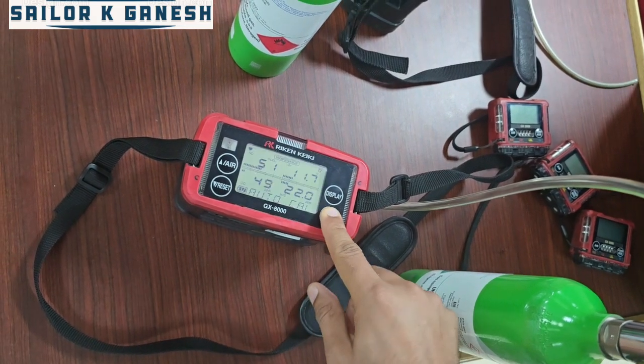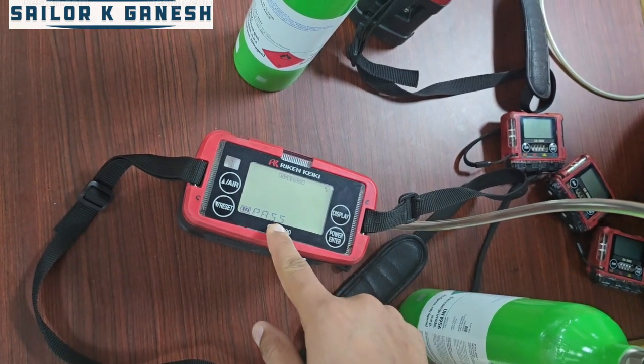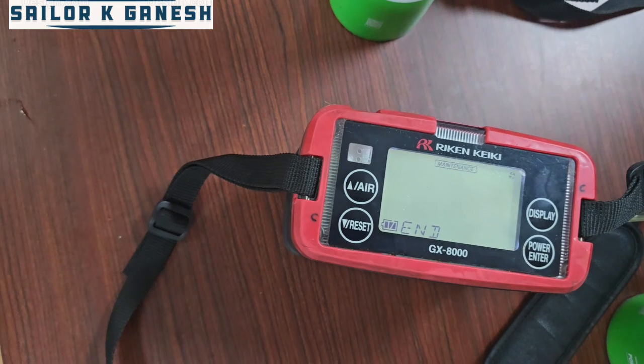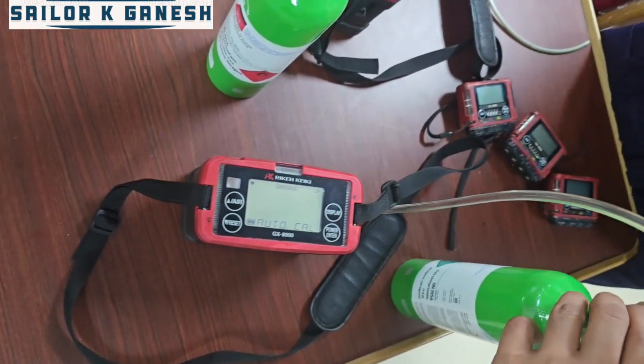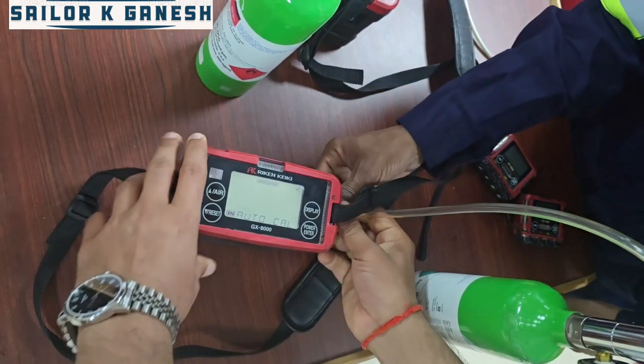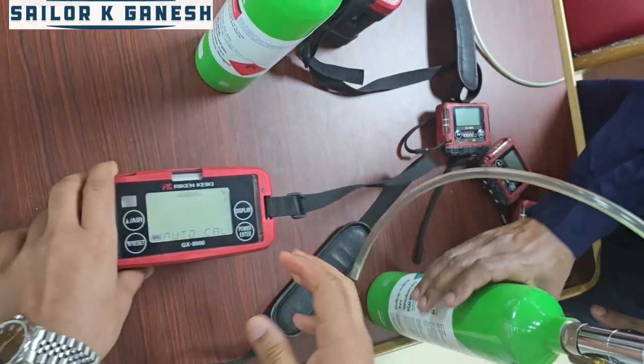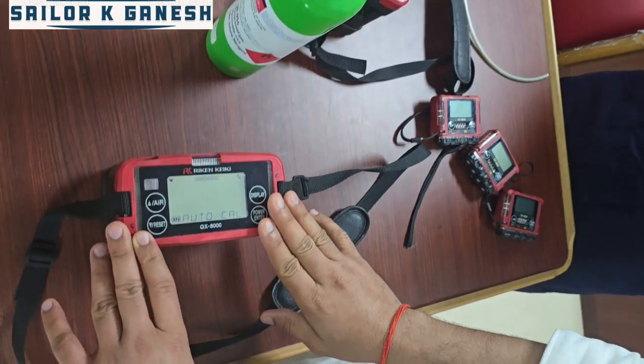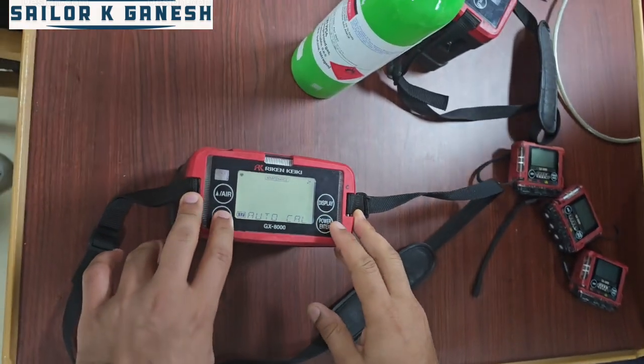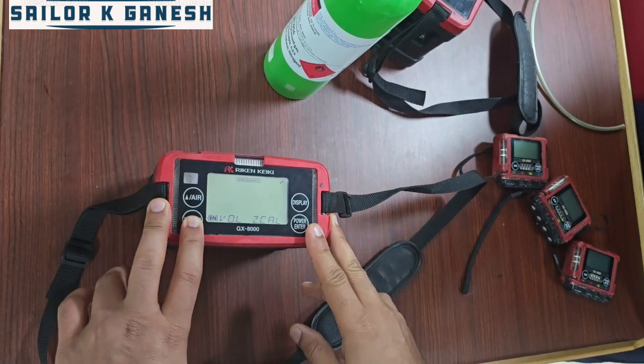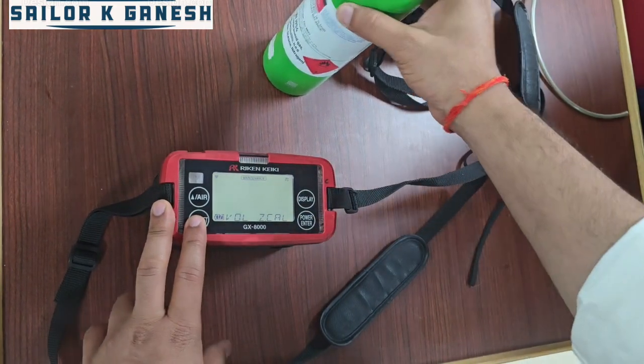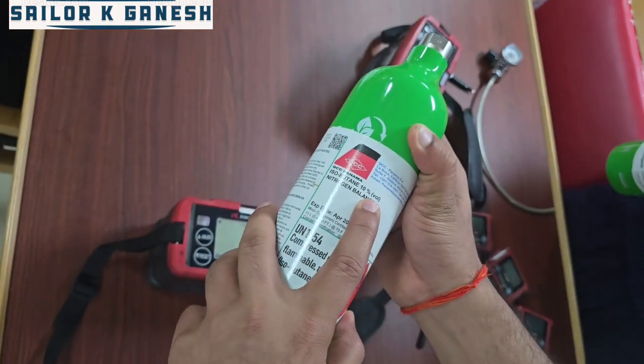Okay, we'll go for enter. Now the test is passed, as you can see over here. Now close your valve and remove it from here. Auto cal is passed. So auto calibration is done for this equipment. Okay, then go next. Volume Z cal. So another bottle we have is isobutane 10% volume.